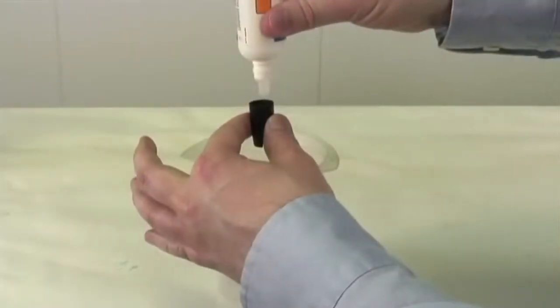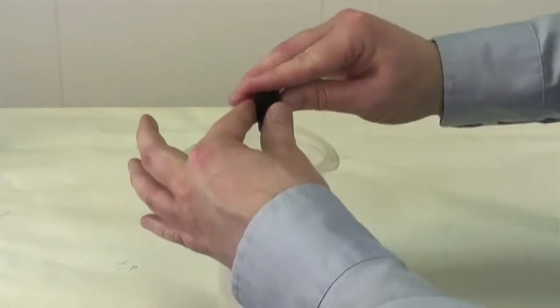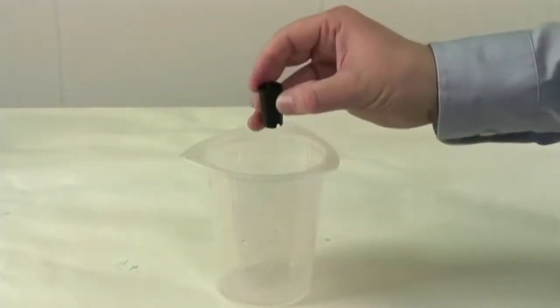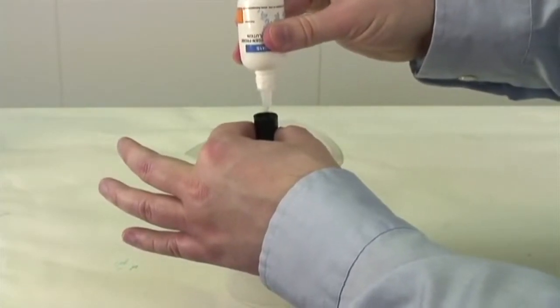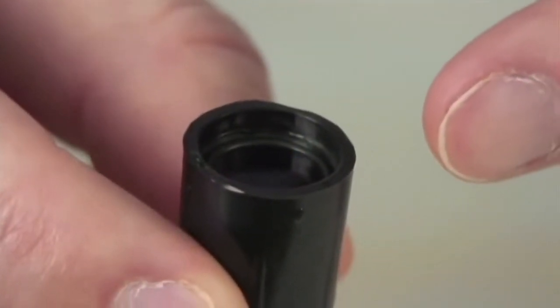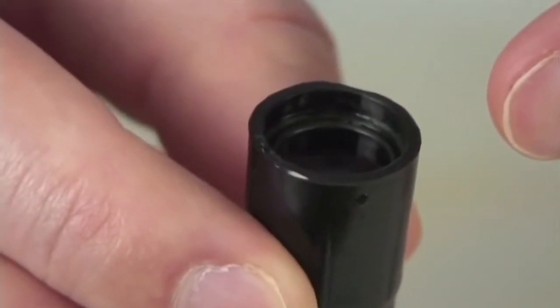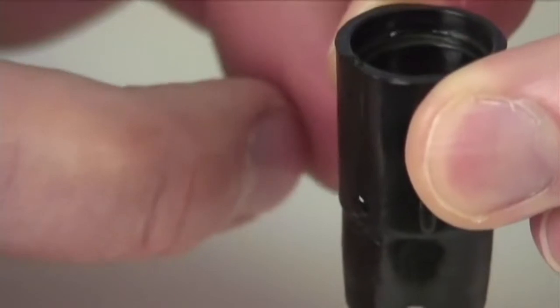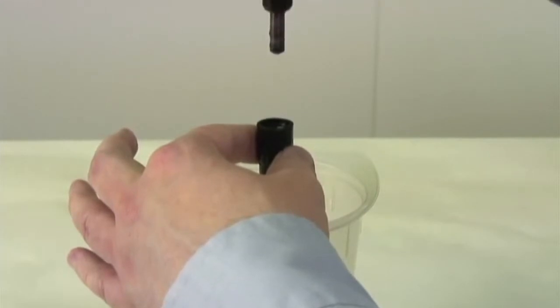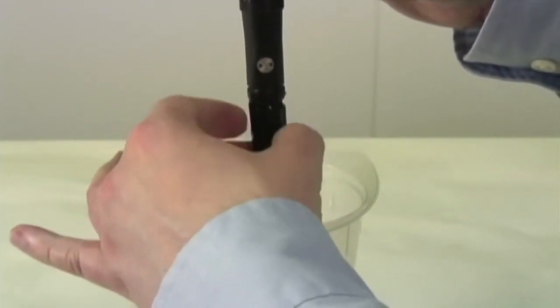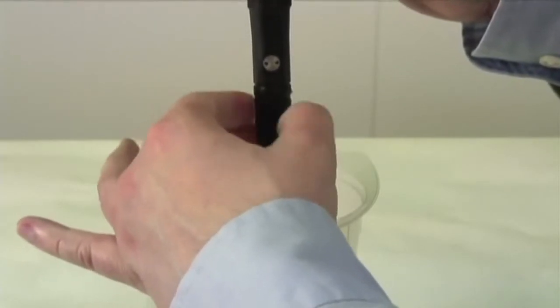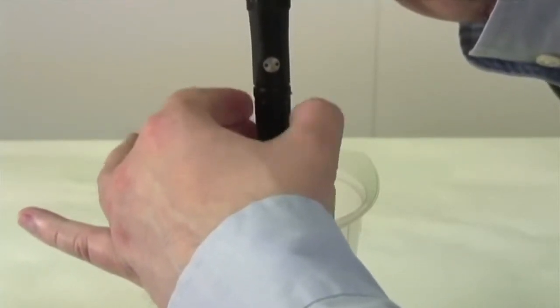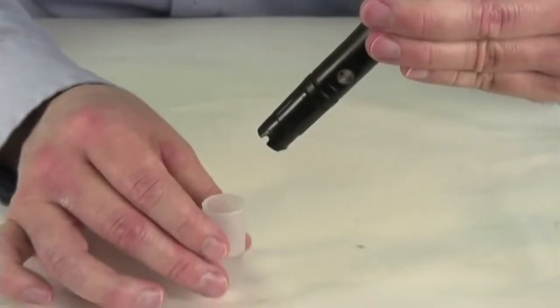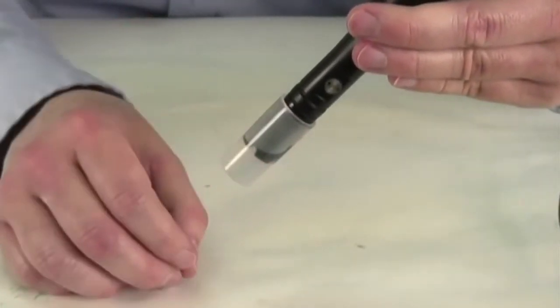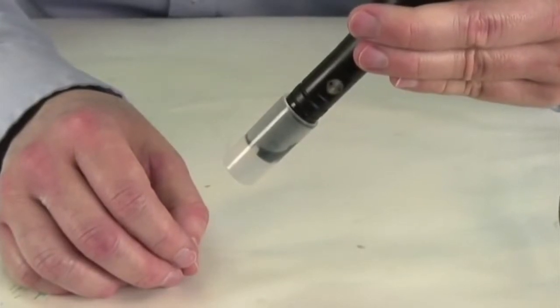Step 5. Prime the cap with electrolyte solution. Shake gently, discard, and refill with clean solution. Step 6. Gently tap the side of the cap to remove any trapped air bubbles. Don't tap the membrane itself, that could damage it. Step 7. Now, with the sensor facing downward, slowly screw on the membrane cap upward and counterclockwise. Some electrolyte will overflow, but that's okay. Step 8. Finally, put the protective plastic cover on the probe. You'll want to use this during polarization and while the probe is not in use. It keeps it safe and in good condition.